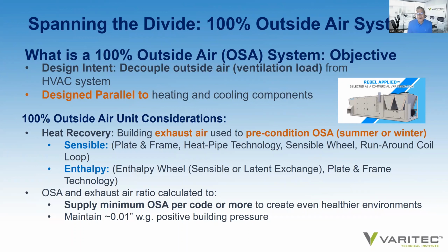So when you use a 100% outside air system, however, you have to make sure that you're exhausting as much air from the building as outside air is supplied, so you maintain a positive building pressure of 0.01 inches. So if you're going to exhaust that much air, why don't we focus that into an exhaust air stream that can be used with a heat recovery solution so the outside air can be preconditioned before it hits the cooling coil. So the design consideration of a 100% outside air unit is a little different from conventional air handling units or package DX configurations.